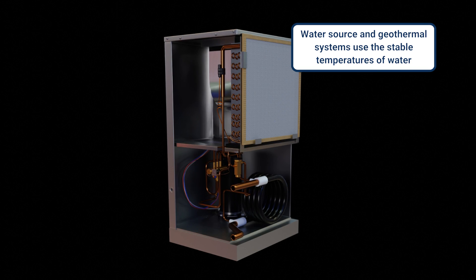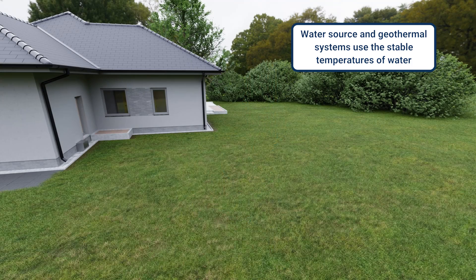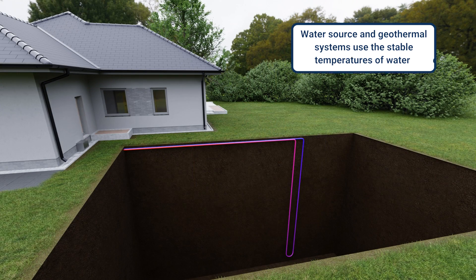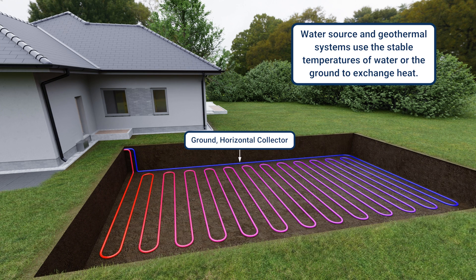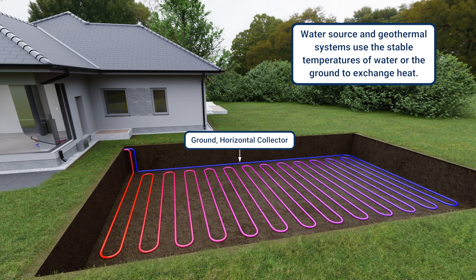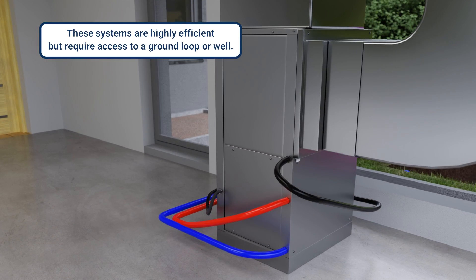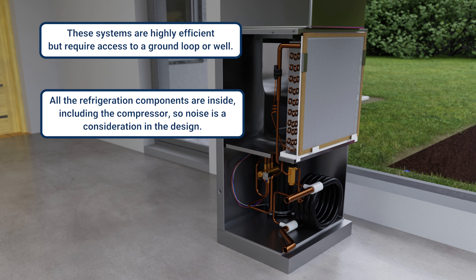Water source or geothermal systems use the stable temperatures of water or the ground to exchange heat, rather than outdoor air. These systems are highly efficient, but they require access to a ground loop or a well. All of the refrigeration components are inside, including the compressor, so noise is a consideration in the design.